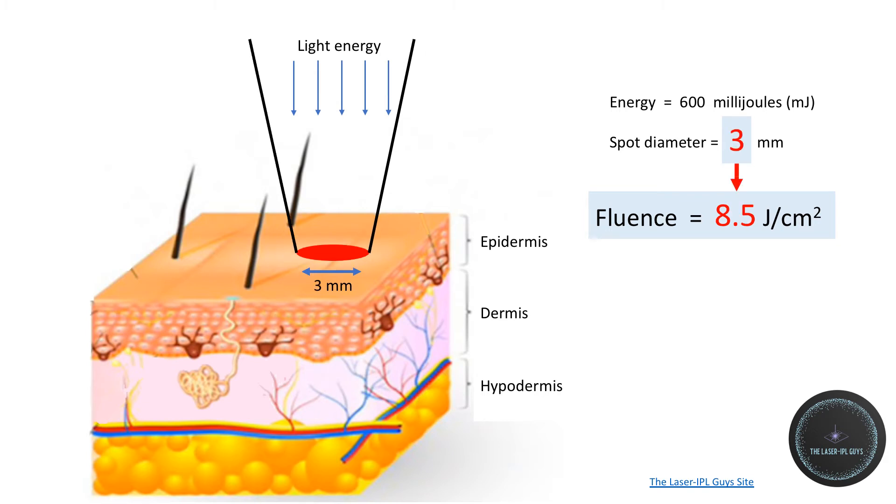If you then use a smaller spot, in this case 3 millimeters, with exactly the same energy as before, then the fluence will increase to 8.5 joules per square centimeter. And the same energy in a 2 millimeter spot diameter will yield 19.1 joules per square centimeter.